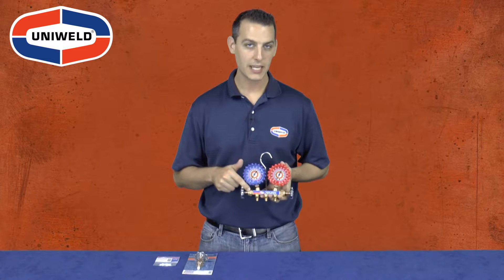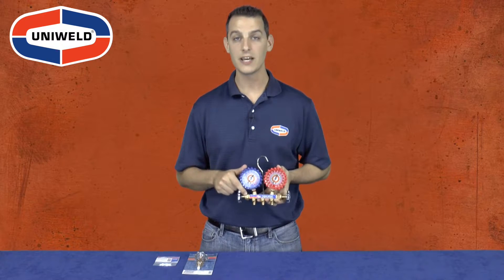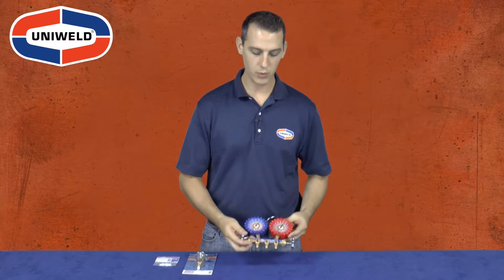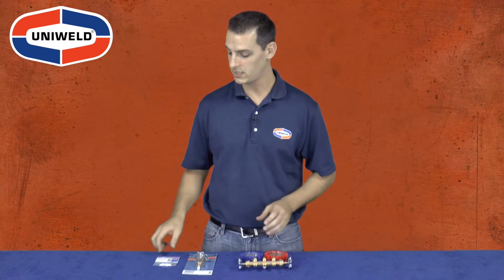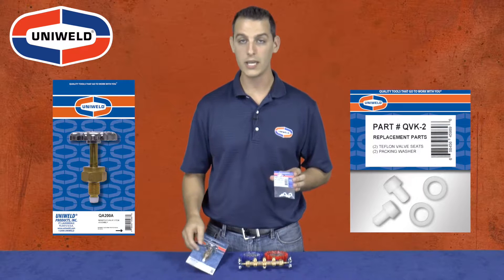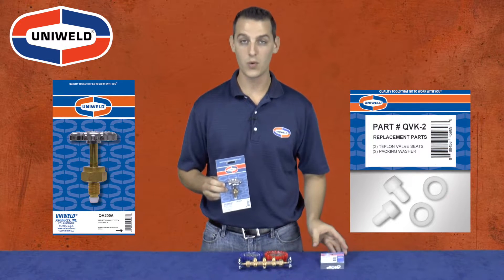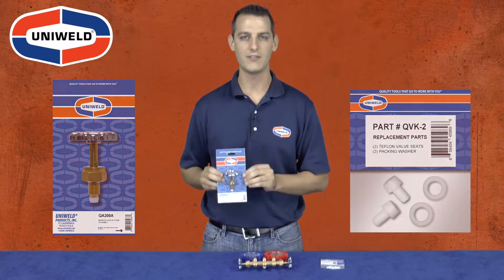After re-tightening the brass packing washer on the manifold body, if the valve continues to leak, then the Teflon seat and packing washer will need to be replaced. This is also a simple repair that can be done two different ways: Uniweld's QVK2 manifold valve repair kit or Uniweld's QA200A full valve assembly. The simplest and most straightforward option is to replace the full valve assembly.